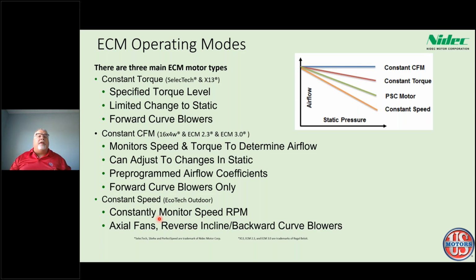There are 3 operating modes that ECM motors are programmed to operate in. The first one is constant torque, and constant torque is a type of ECM product that, as you can tell in the name, we, or the OEM, will program with specific torque levels. Those torque levels will be unique based on the system that they're actually producing.